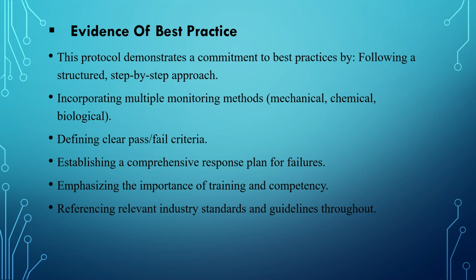If the BI passes, we proceed on to sterilization. If the BI fails, then we have to quarantine. All the RMDs that we have processed have to go under quarantine and have to be reprocessed after 3 consecutive loads have confirmed that there is no issue with the BI failure. It's going to pass. Also, the BI can be an issue with crushing, how you crush the BI. If it has not been properly crushed, that means there is an issue with it. Then we have to redo the BIs so that it passes.